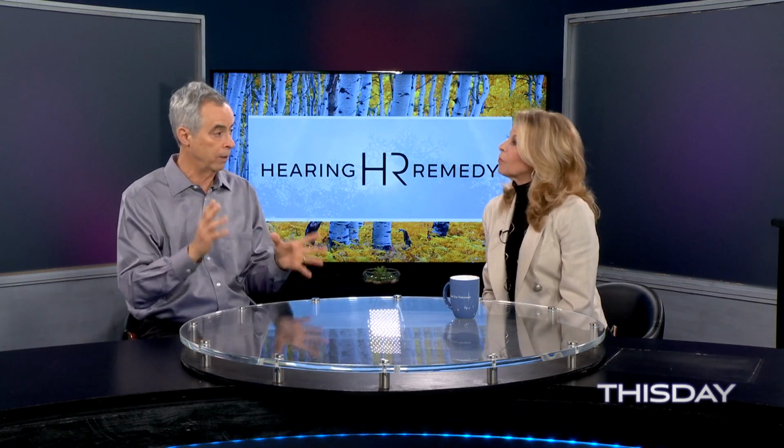That's the information, the starting point for doing an adjustment on a hearing aid. We do a lot more on top of that. We actually do another test with the hearing aid in place, because the acoustics change when you put all these pieces in your ear, and that acoustic change alters the frequency measurements we've done. If we do the test with the hearing aid in place exactly the way they're going to be wearing it, we get a much better fit and a much better success rate.